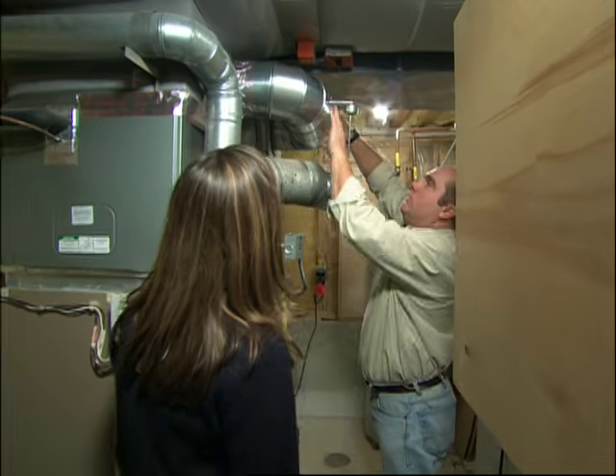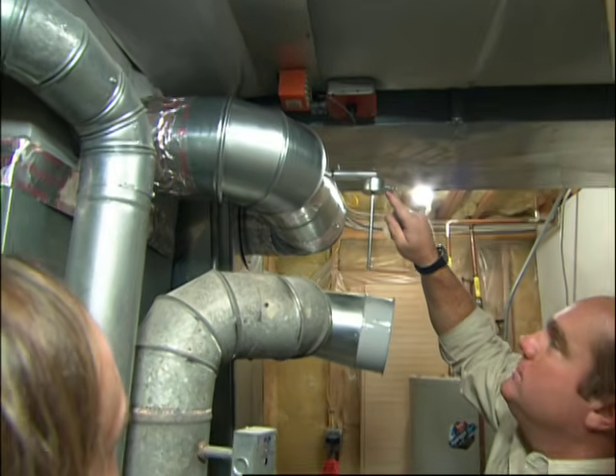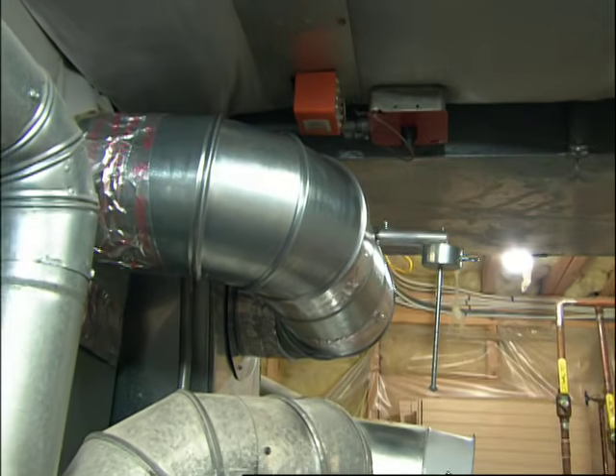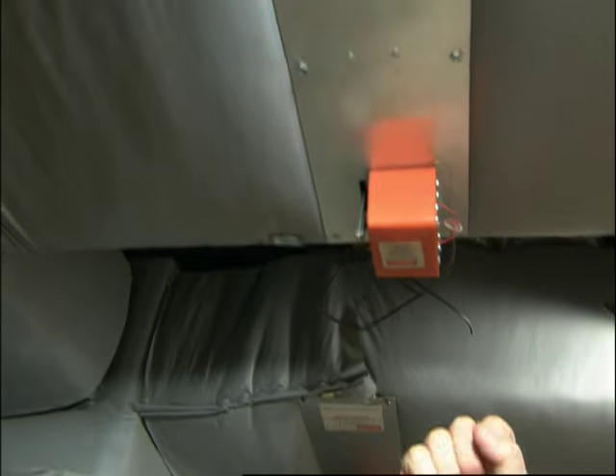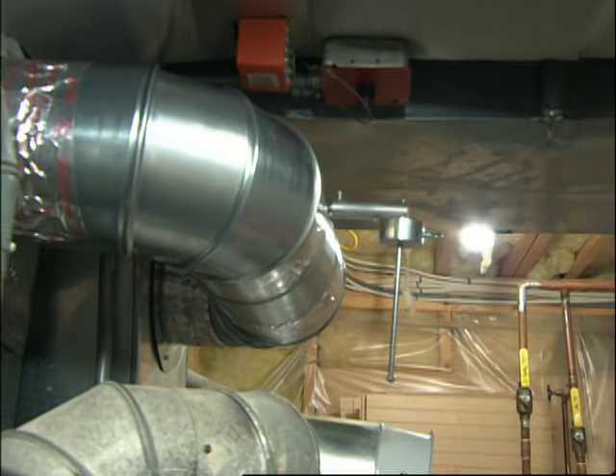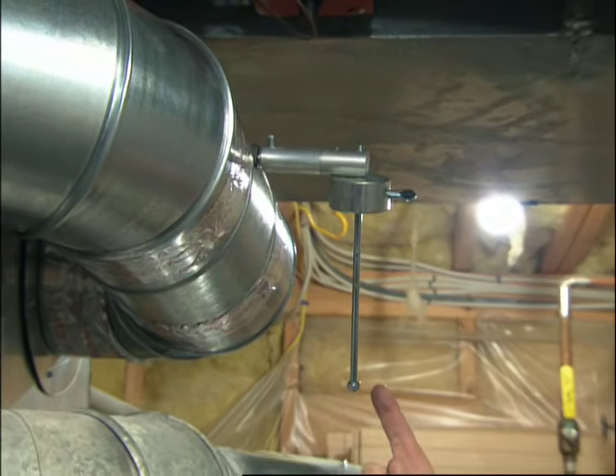All right, we have sealed all of our new connections. I've adjusted the weight on this bypass damper arm. First floor thermostat is closed. Second floor is open. Now it's time to turn the furnace on. All right, we do. The bypass damper should open.